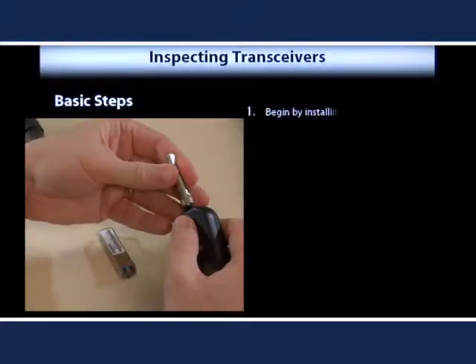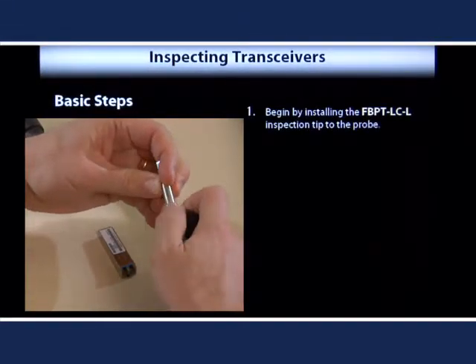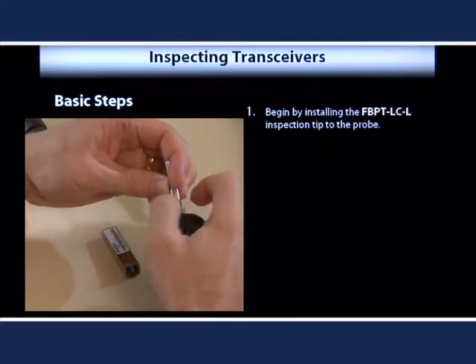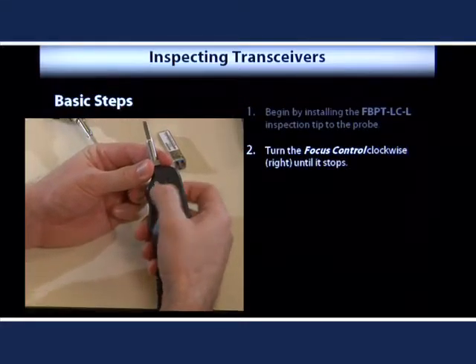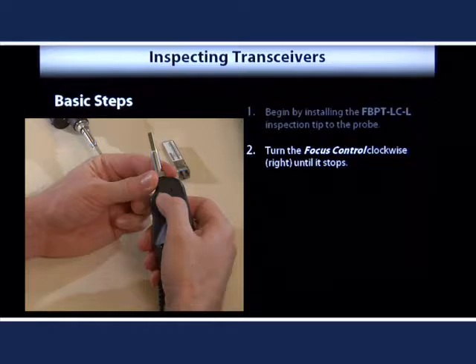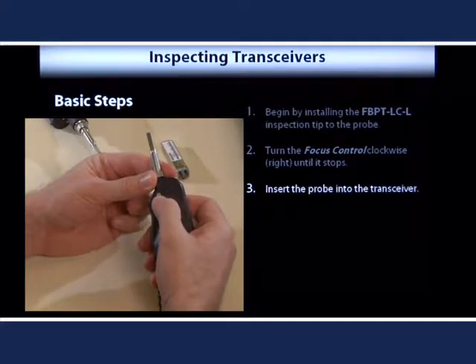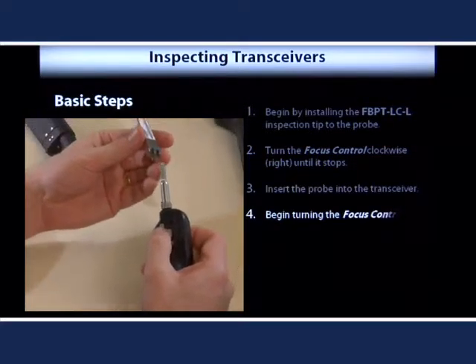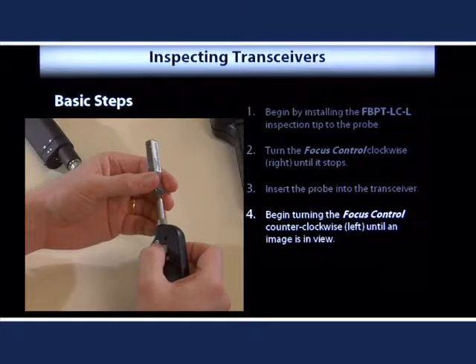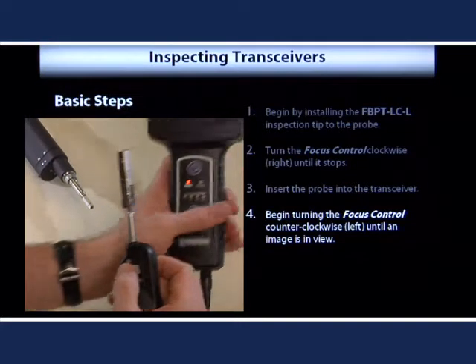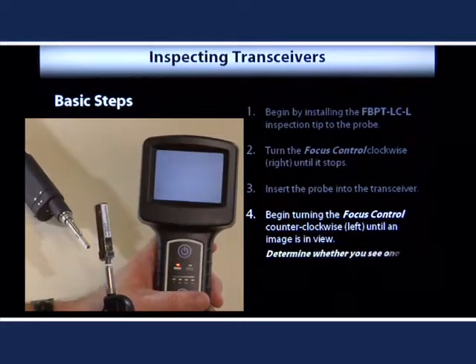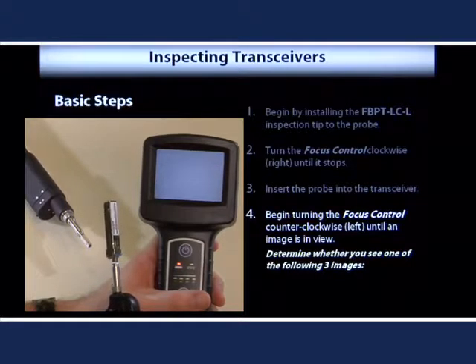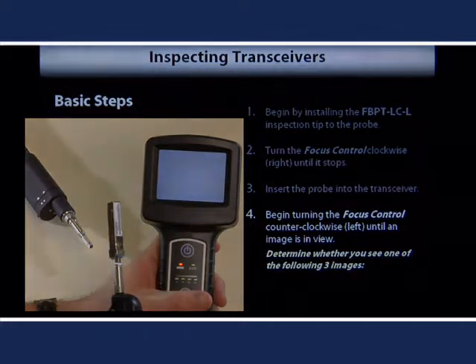Begin by installing the FBPT LCL inspection tip on the probe and turn the focus control on the probe clockwise until it stops. Now insert the probe into the transceiver and begin turning the focus control counterclockwise until an image is in view and in focus. At this point, you will need to determine whether you see one of the following 3 images.